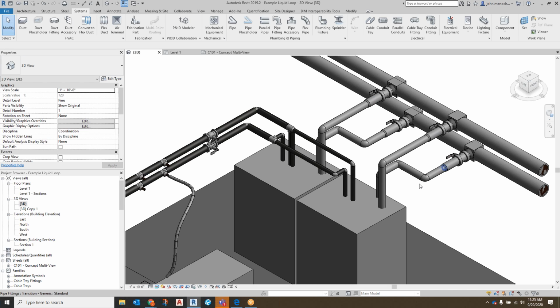So this equation - a lot of people on here can work this equation and come out with something. One of the other discussions we've been having is how do we quantify what we recommend, or what's available to you, based on both the water temperature and pressure conditions, but also the size of the pipe. One way is to say, well, right now in our data center we have this 8-inch header with a bunch of 4-inch drops that were for crays, or for future use. What can we get out of that for total power if we had 100% effectiveness?